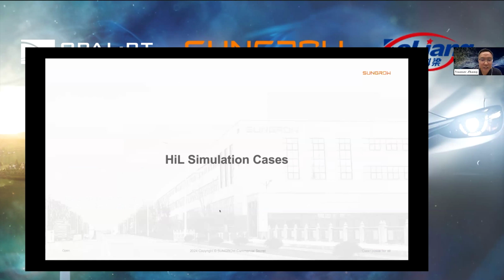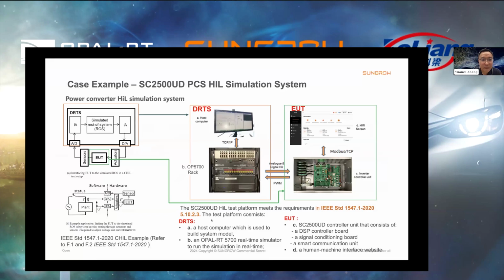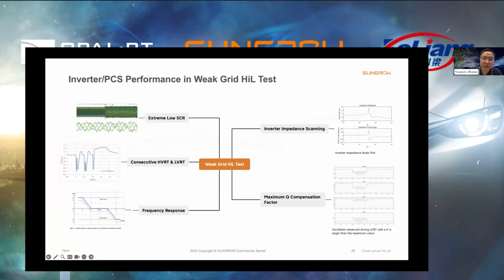Here I'll share some simulation cases we've done previously. The first and simplest is one inverter controller connected to one real-time simulator to run all kinds of grid connection tests. We built a weak grid HIL test platform to test both grid-forming and grid-following control strategies, including extreme low SCR conditions, pushing them to the limit to see the lowest SCR the inverter can work at. We also perform consecutive high voltage ride-through and low voltage ride-through tests, as well as frequency response tests.